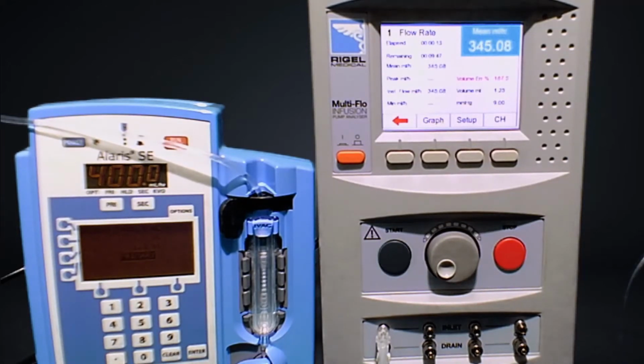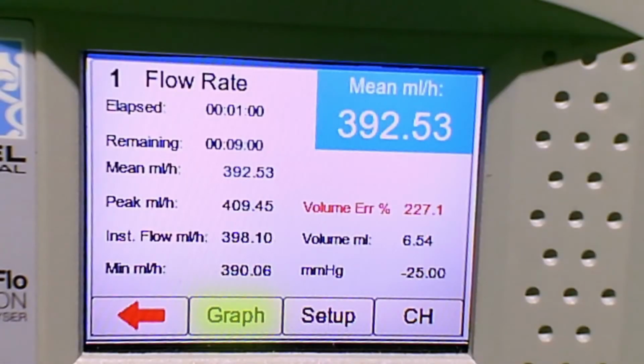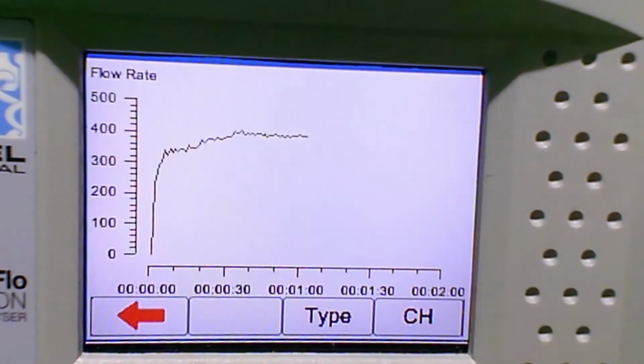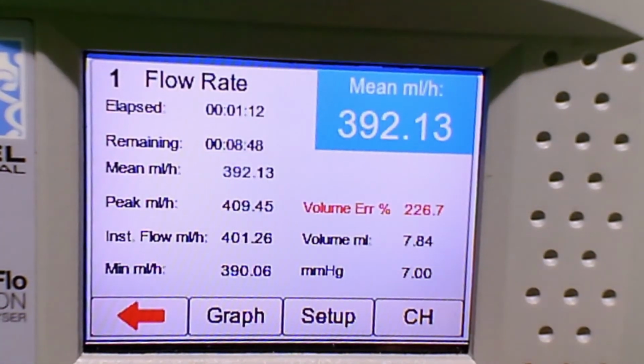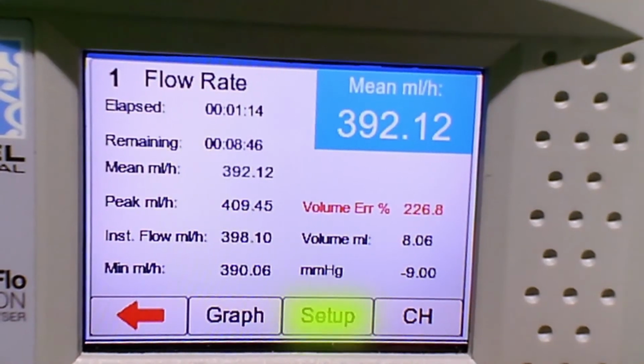Okay, so now we're running. We've got the instant flow rate shown on screen, not very clear, but it's the second from bottom, and then the mean mil per hour. So the reason that's low is because it's not actually reached the full stage. There's that initial trumpet curve whereby the pressure has to overcome pressure in the circuit before reaching, and that shows in this diagram here. So we've got the flow rate is now achieved, and the mean flow rate will gradually come up.